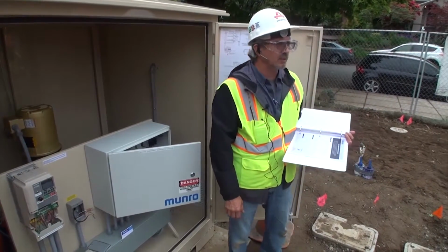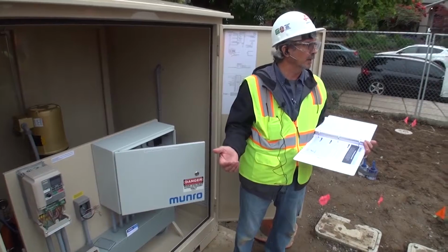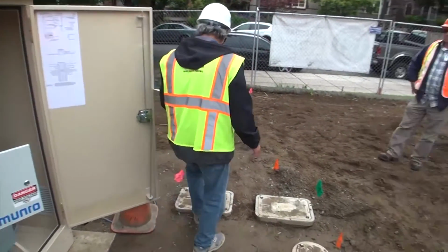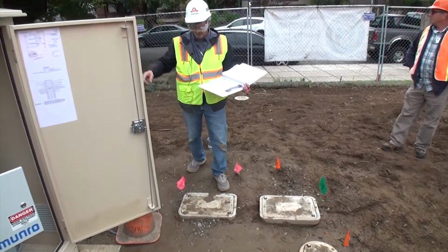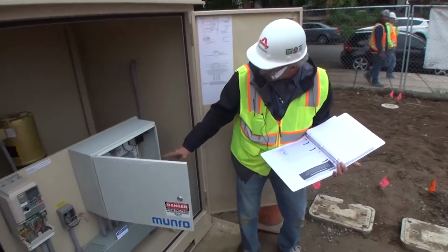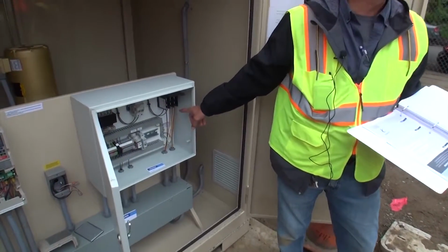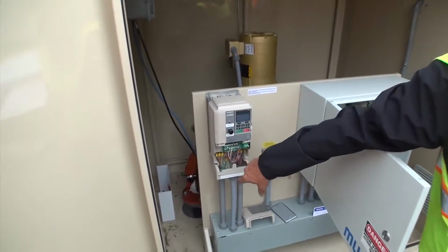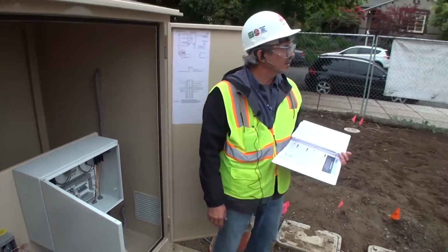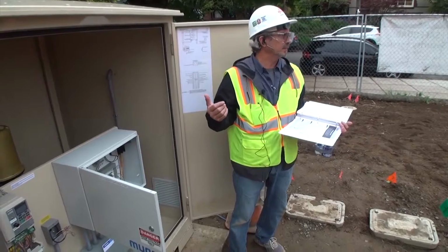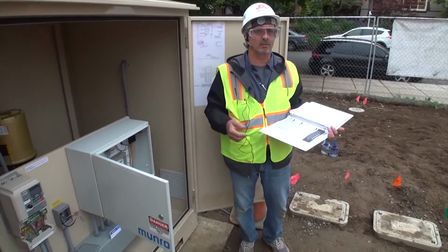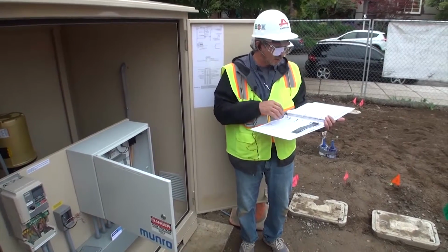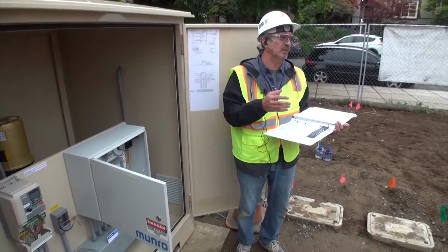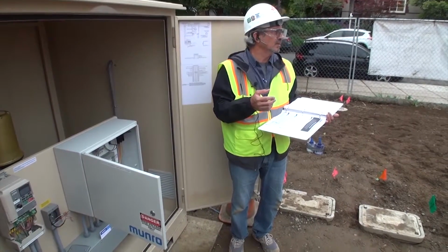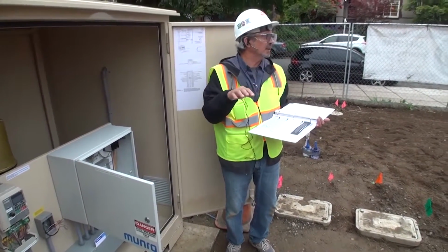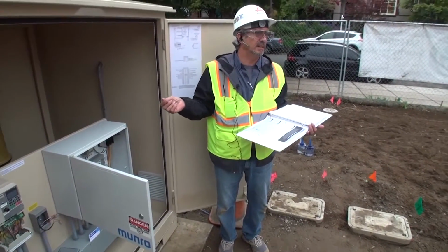Voltage unloaded just means what your voltage is when the motor is not running. You can do this at the disconnect out here, or open this up and do it on the junction blocks right there. That basically tells us the condition of the power you're feeding it, if you have a brownout or an electrical problem. To be honest, a more important measurement is your voltage loaded. If your voltages are all even when you start out, and then you put a load on it and they become very uneven, that tends to indicate a bad connection.